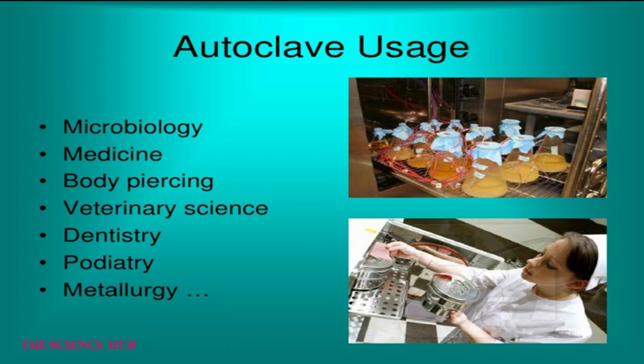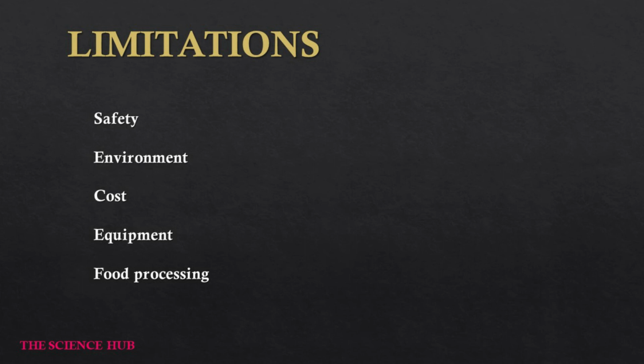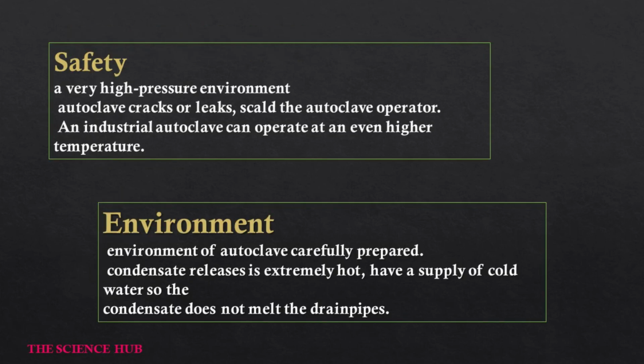Autoclave usage. Autoclaves are used in microbiology, medicine, body piercing, veterinary science, dentistry, podiatry, metallurgy. Limitations: safety, environment, cost, equipment, and food processing. Safety. A very high pressure environment; the autoclave may crack or leak and scald the operator. An industrial autoclave can operate at an even higher temperature.